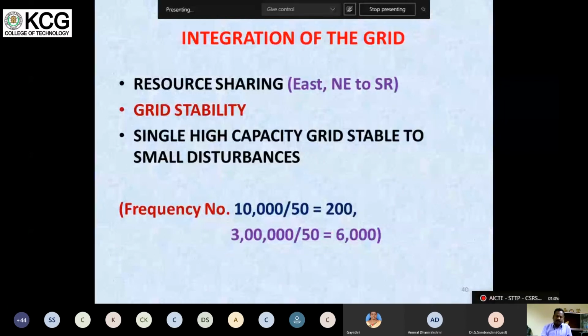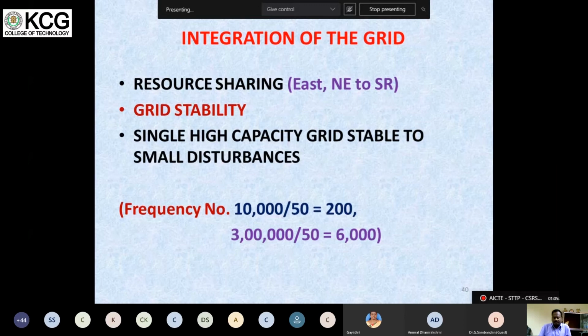Now you can see why we go for integration of the grid. After that, we will go for the failure. Why should we go for integration of the grid? This is resource sharing. From the eastern region and northeastern region, power can be transferred to the southern region. It leads to grid stability. A single high capacity grid is stable to small disturbances. For example, if we take a grid of 10,000 megawatt, 10,000 divided by 50 is called the frequency number, that is 200. That means in a 10,000 megawatt grid system, if a 200 megawatt generation failure occurs, the frequency will go down to 49 Hz, that is one Hz lesser.